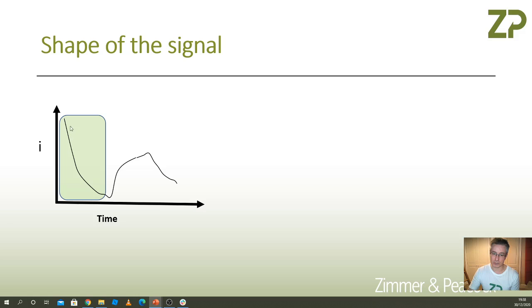In the first instance, when he turned it on, the signal was in zero millimolar. At this point he spikes it with some glucose and it comes up. If he left it, the signal will come down again because the glucose is being depleted and you have what's called diffusion limitation. The molecules can't arrive quick enough to keep up with the way the enzyme is producing hydrogen peroxide and so the signal decreases because you're building up what's called a diffusion barrier.